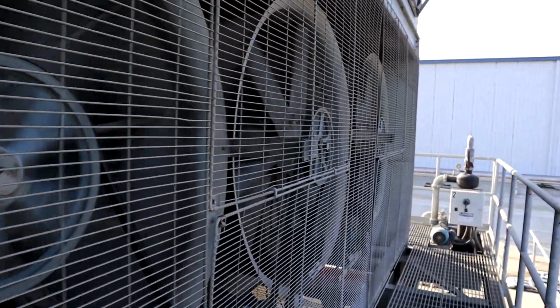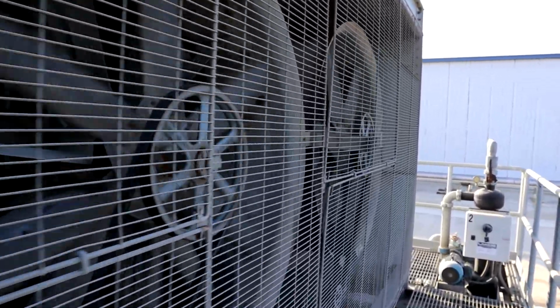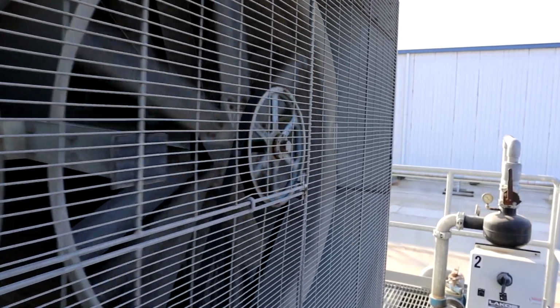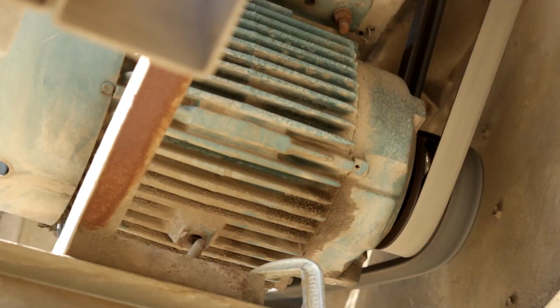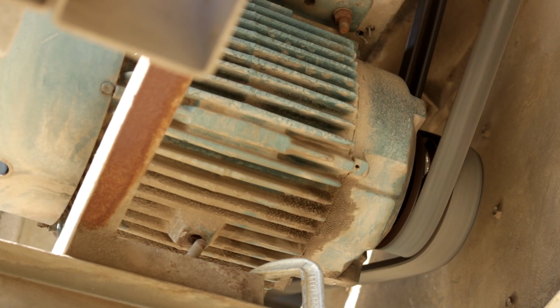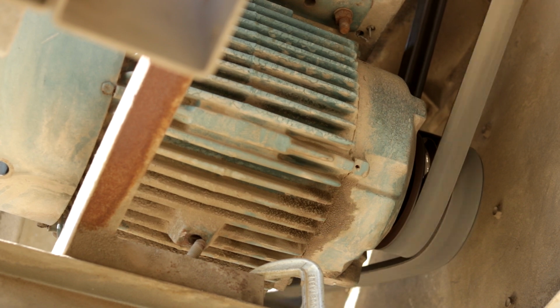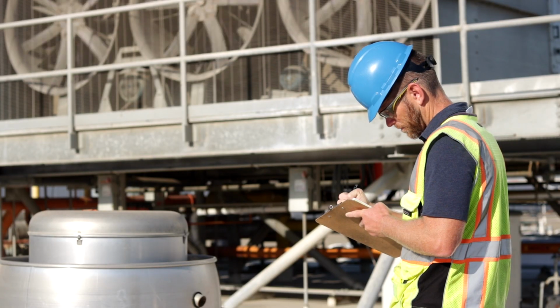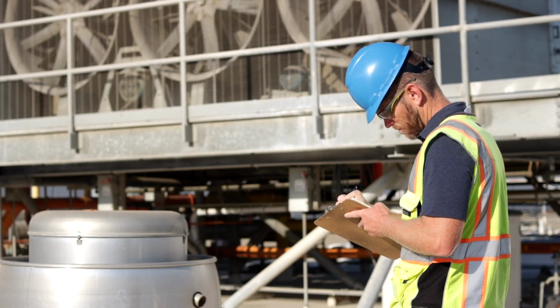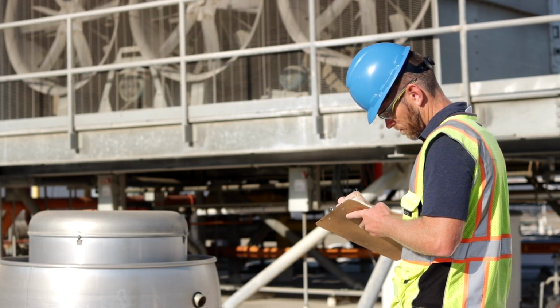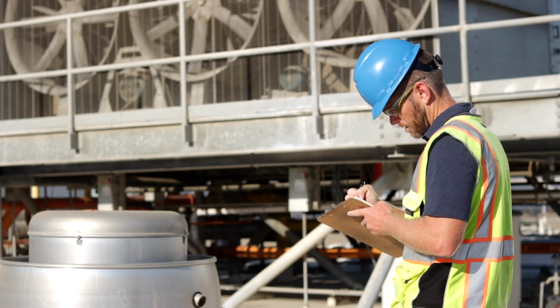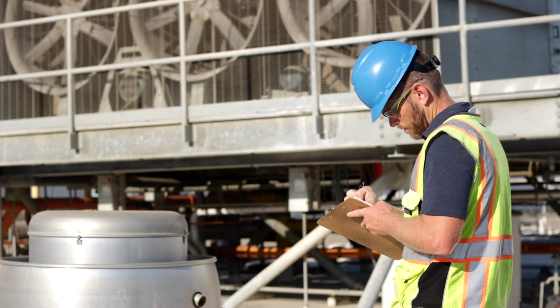For example, if a system has 5 condensers and 1 fan belt breaks, the consequences are minimal. Therefore, a facility may opt to keep extra belts in stock and replace them when they break instead of replacing the belts on a calendar or runtime basis. The big idea is that not all maintenance activities are equal. An operator must understand what is critical to safety and overall system performance and make sure that those tasks are being performed.